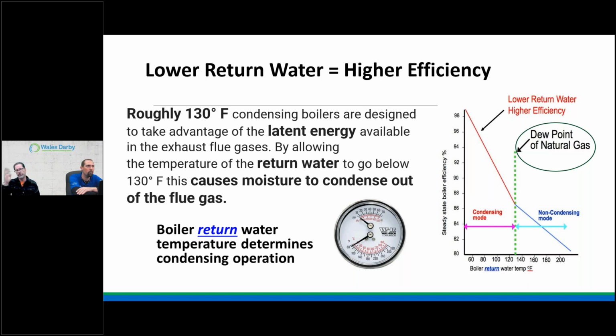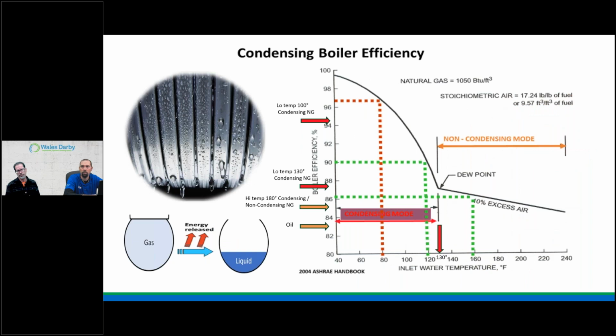But then we have what they call the dew point, and that's something we have to be aware of as well. With this dew point, that's where we're going to see lowering water temperatures following a dew point line that we'll have to use a combustion analyzer for, right? So maybe some of our techniques in setting up boilers will also change, and that's using a combustion analyzer. So the dew point there is really key.